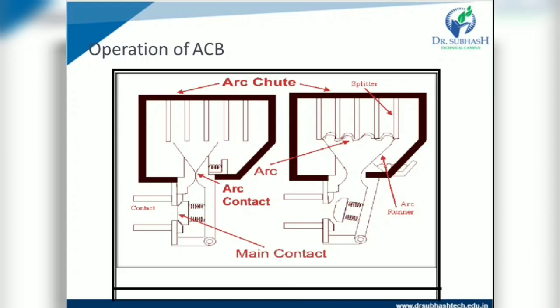The arcing contacts are hard, heat resistant and usually of copper alloy. Arcing contacts are used to relieve the main contacts from damage due to arcing. The arcing contacts are easily renewable when required. The auxiliary and arcing contacts close before and open after the main contacts during operation.